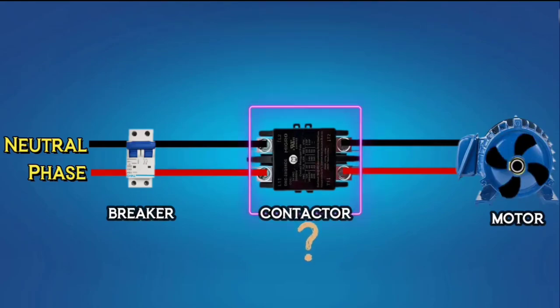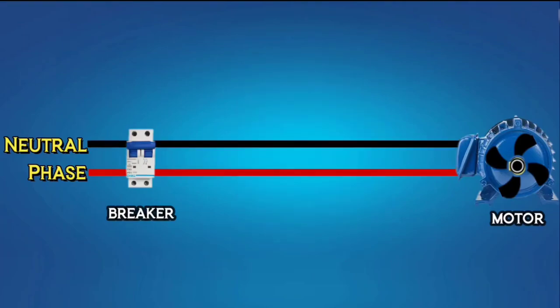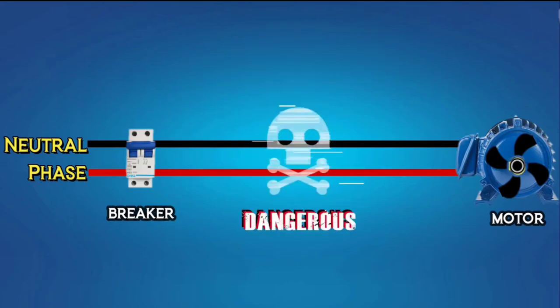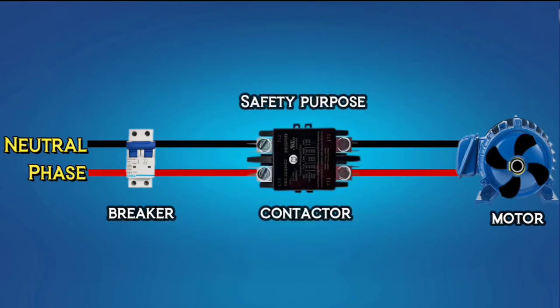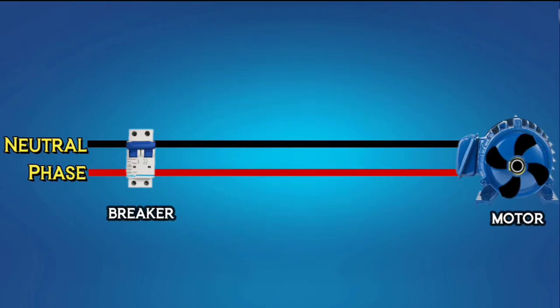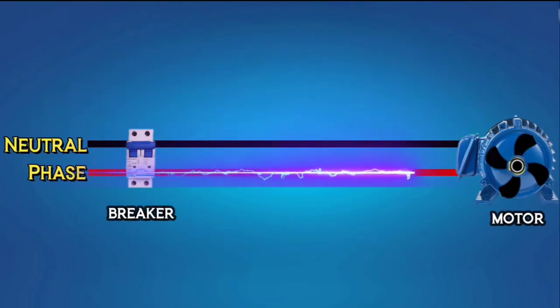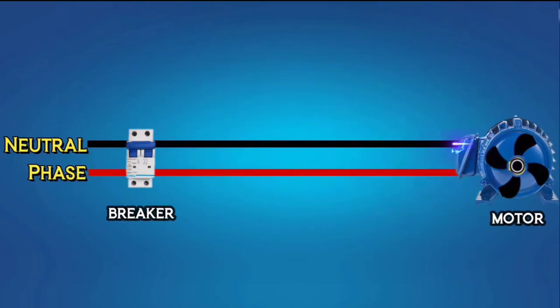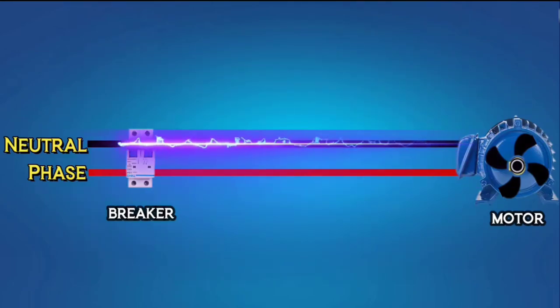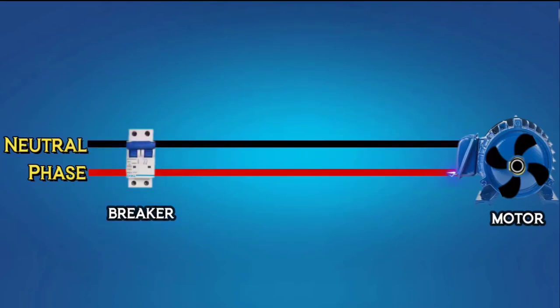Why should a contactor be used? What happens if you connect the motor directly to the power supply without a contactor? That way you can connect directly, but connecting directly like that is not safe, because we use a contactor only for safety reasons. If a motor is connected directly to the breaker without a contactor, it is necessary to directly operate the breaker to turn the motor on and off, through which the high current goes. If electricity leaks in the breaker due to equipment fault, it becomes life-threatening.